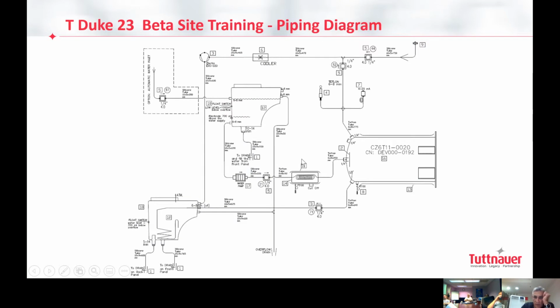We know already the mineral free water system with the Ulka. You see it? Solenoid vaporizer to the chamber. Of course, we have a baffle here. When the steam is coming, it will not just kick the load which is placed right here. So there is a plate here, like a baffle. Then we have the exhaust, fast exhaust channel with the coil. Then we have the vacuum system from here. The valve, chiller, vacuum pump down there.